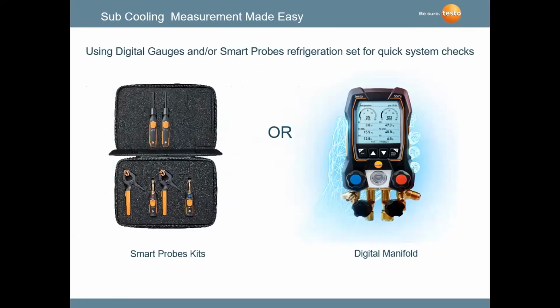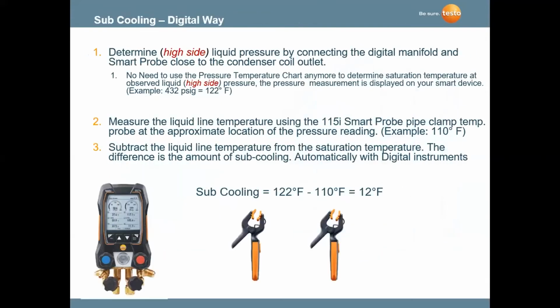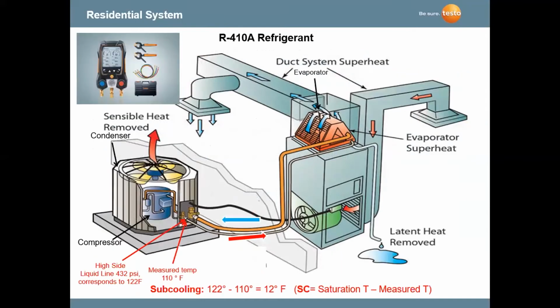Again, we're back to digital gauges today. A full line of instruments, whether you're starting at $100 or going all the way up to $600-700, depending on the type of instrument or configuration you're looking at. But again, we're on the high side of the system. We're using wireless probes, and we have two of them here, one on the low side, one on the high side. So we're taking both the superheat and subcooling calculations into account with one instrument, not going back and forth doing your measurements.